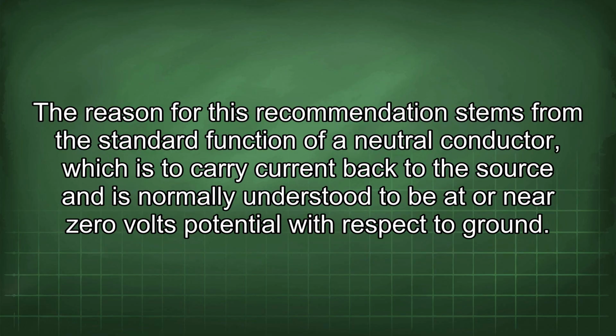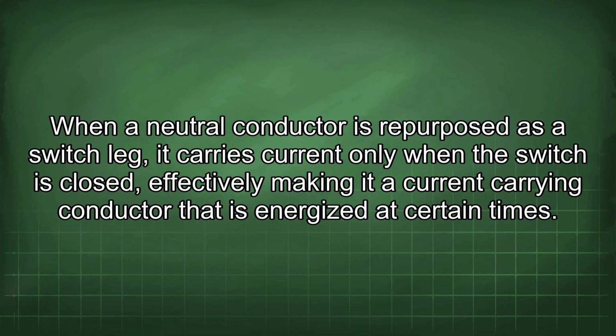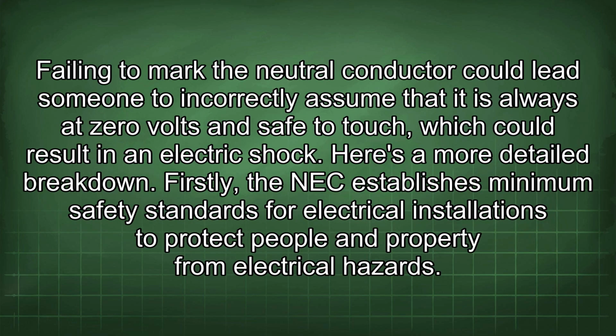safety. The reason for this recommendation stems from the standard function of a neutral conductor, which is to carry current back to the source and is normally understood to be at or near 0 volts potential with respect to ground. When a neutral conductor is repurposed as a switch leg, it carries current only when the switch is closed, effectively making it a current-carrying conductor that is energized at certain times. Failing to mark the neutral conductor could lead someone to incorrectly assume that it is always at 0 volts and safe to touch, which could result in an electric shock.